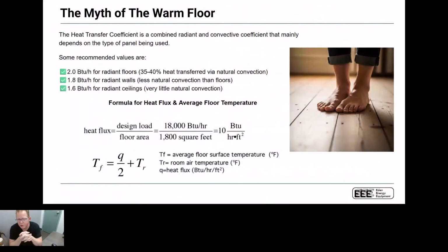One of the things I would like to touch on that we've gone through before is understanding that myth of the warm floor. The objective with us designing a hydronic heat system is we're not trying to drive BTUs into the body. We're not trying to overheat you. We're trying to keep the space comfortable. There's a misconception as we look at the heat transfer coefficient of either a floor or a wall or a ceiling that we're trying to deliver a lot of BTUs into that space. But the reality is, if you looked at a modern load at 18,000 BTUs, which seems insane, but if you look at a lot of the new houses that are being built, most of them are taking a 1.5 to 2.5 ton heat pump, and you convert that into BTUs, and you find out that the 18,000 BTUs per hour in a new building is commonplace, which means you only need 10 BTUs per square foot.